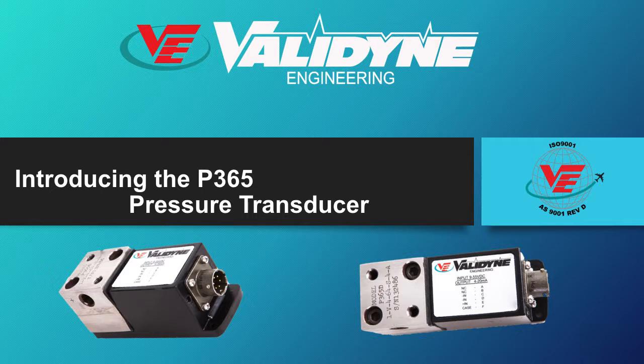The P365 transducer is rugged, available in a wide variety of differential pressure ranges, and operates at up to 10,000 psig static pressure. The P365 provides standard output signals, accepts liquids and gases, and provides outstanding performance over wide temperature ranges. This video will describe the many features of the P365 and provide details about its capabilities.